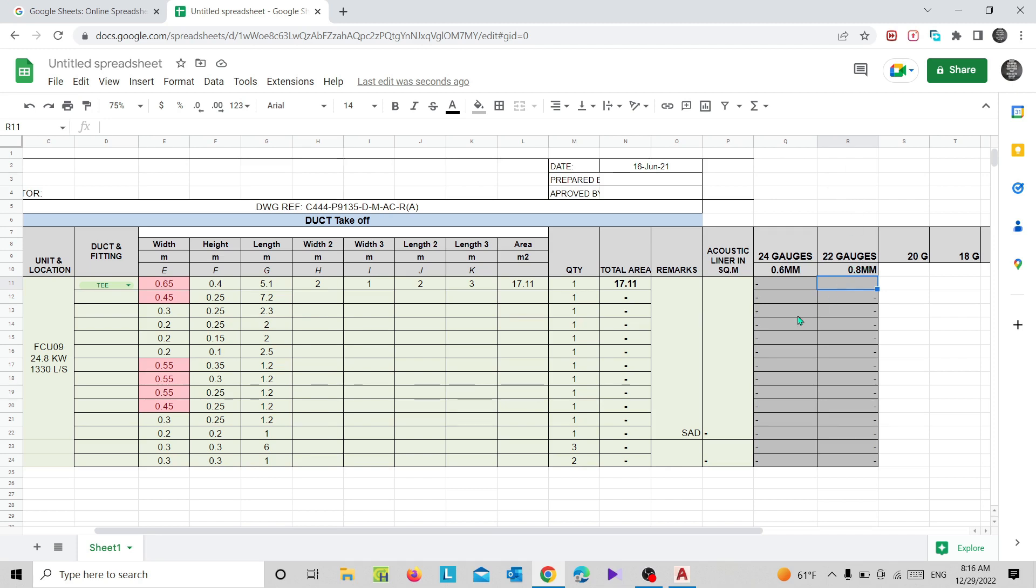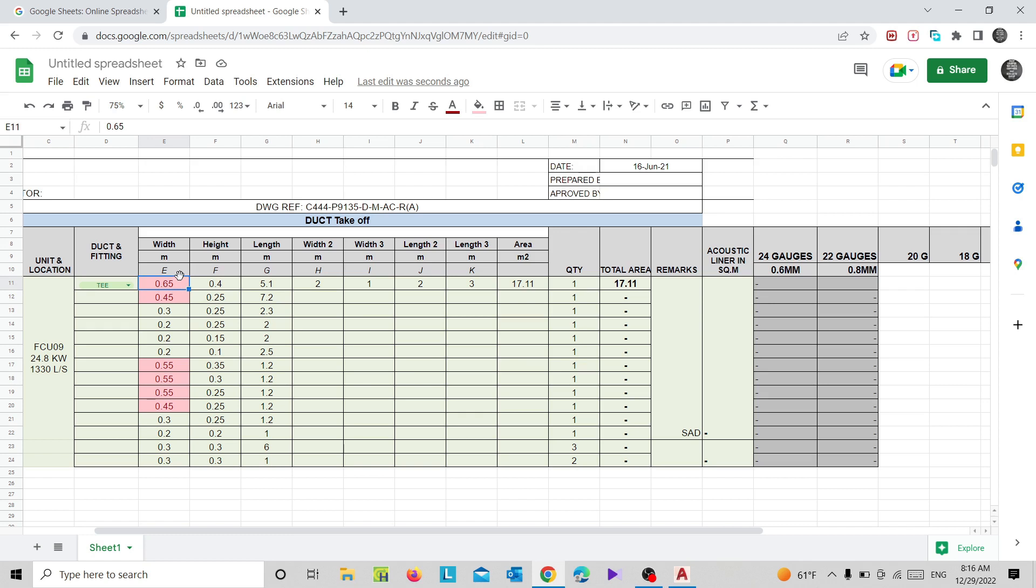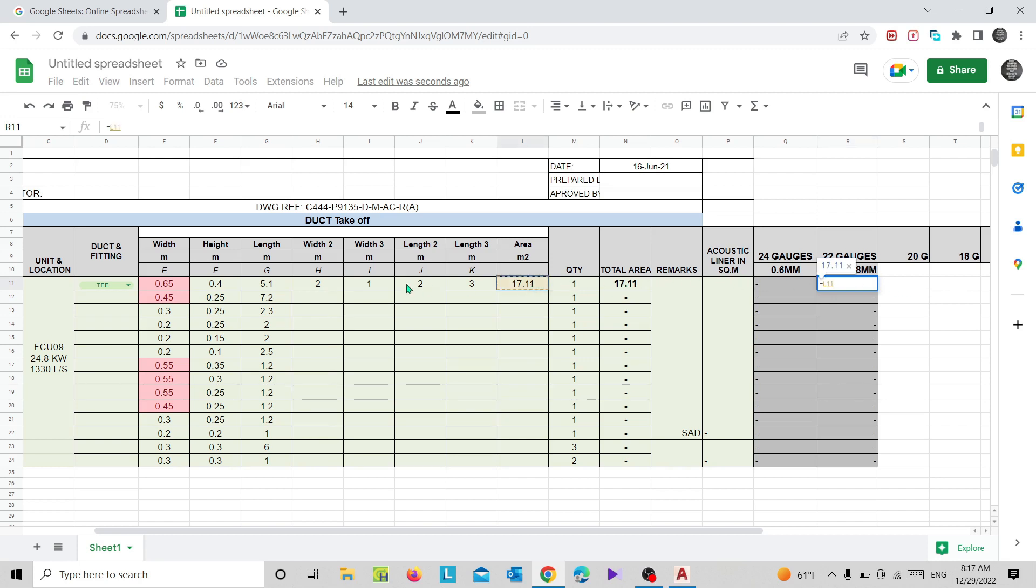Once you find out - for example here we have width of 0.65 and height of 0.4. Where will it come? It already exceeds 400mm. It's in meters, so that could be 0 to 0.4 meters. Here it exceeds 0.4 meters, so it will come on the 22 gauge. For the 22 gauge, the duct sizes could be from 0.4 to 0.8 meters. You can just simply press equal sign, then you can choose the same area value in here. You can see the value came up. This is how you can use this duct gauge.